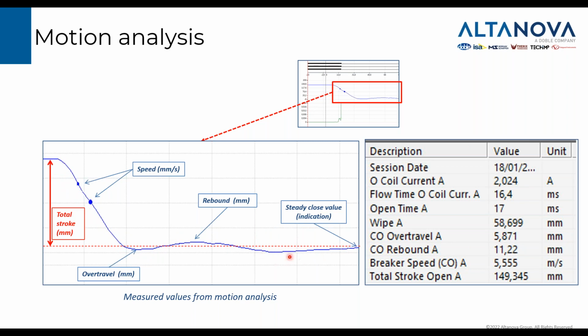Once you have this graph from the transducer, then you can do some automatic calculation. For example, as we said many times, the total stroke, the speed, the over travel, where the over travel is when I reach the final position, but I will go over. Then there are some oscillations. That's why we have a measurement called rebound. And then we get to the steady position. So all this information is important and must be measured and kept under control. All these measurements are performed automatically by CDA 3000.